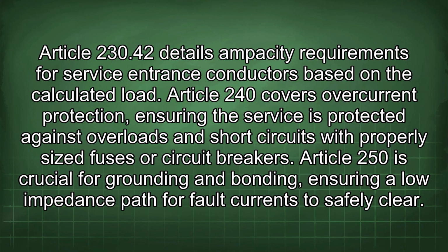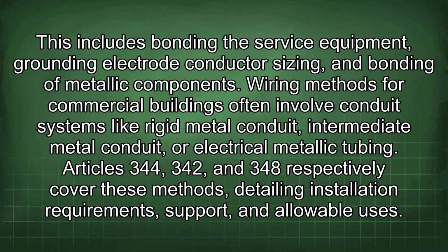Article 230.42 details ampacity requirements for service entrance conductors based on the calculated load. Article 240 covers overcurrent protection, ensuring the service is protected against overloads and short circuits with properly sized fuses or circuit breakers. Article 250 is crucial for grounding and bonding, ensuring a low impedance path for fault currents to safely clear. This includes bonding the service equipment, grounding electrode conductor sizing, and bonding of metallic components.